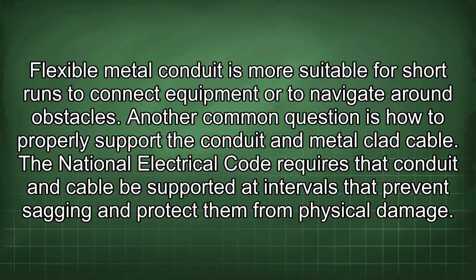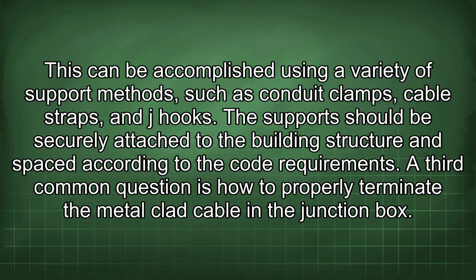Another common question is how to properly support the conduit and metal-clad cable. The National Electrical Code requires that conduits and cable be supported at intervals that prevent sagging and protect them from physical damage. This can be accomplished using a variety of support methods, such as conduit clamps, cable straps, and J-hooks. The support should be securely attached to the building structure and spaced according to the code requirements.